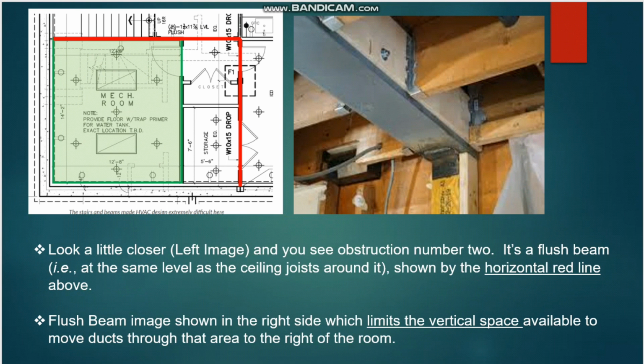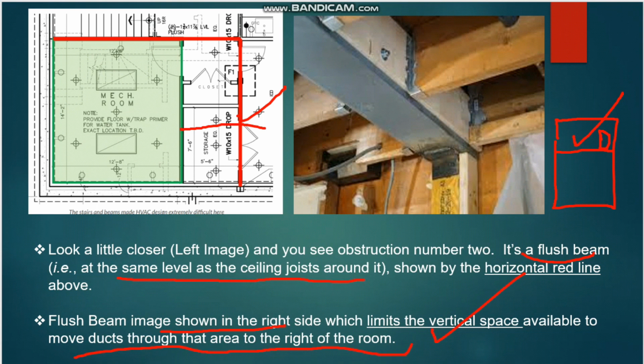But we have another issue here. Let's take a closer look. You can see the red highlighted line. This is obstruction number 2. It's a flush beam, at the same level as the ceiling, shown by the horizontal red line. If you see the section of the room, this is the ceiling, and here we have the flush beam, so it limits the vertical height for passing the duct. The flush beam image shown on the right side limits the vertical space available to move the duct through to the right side of the room. So now we cannot pass the duct here, and also here. So we have two obstructions in different places.